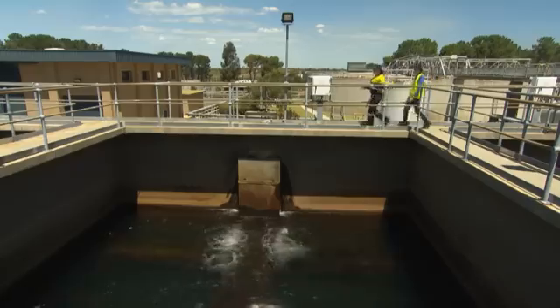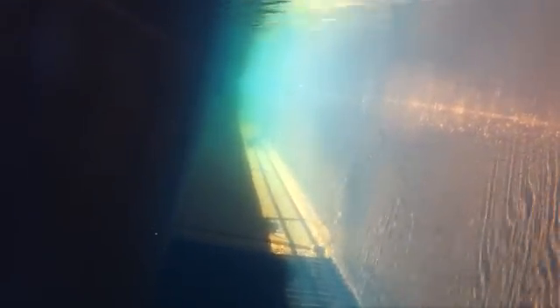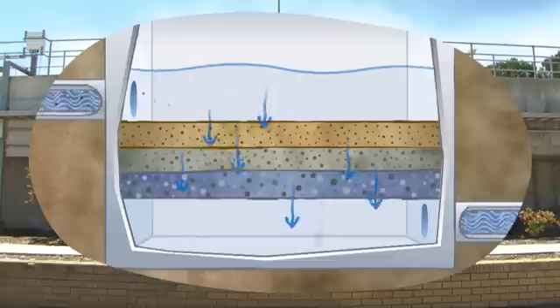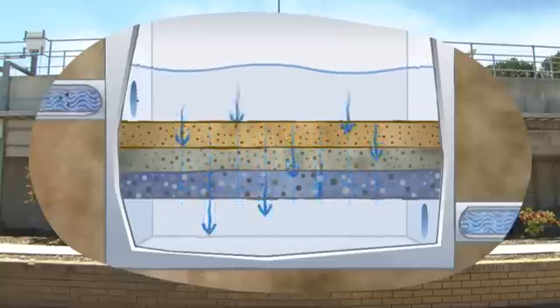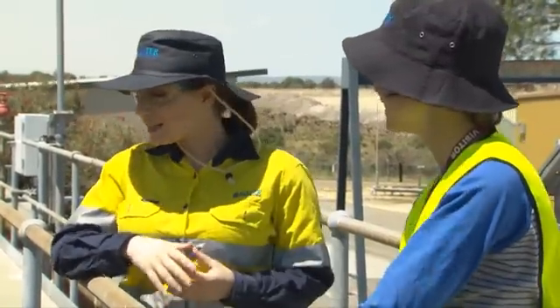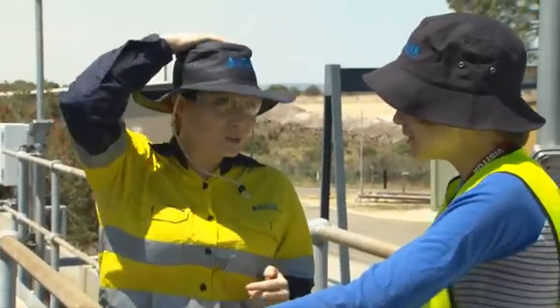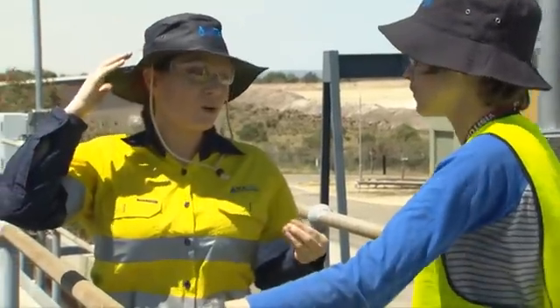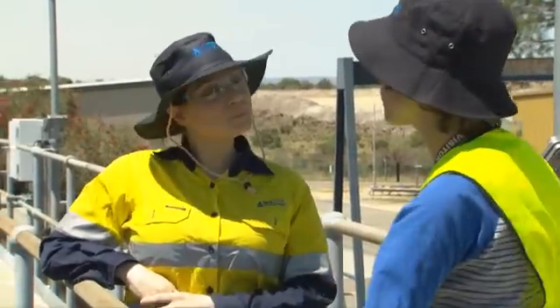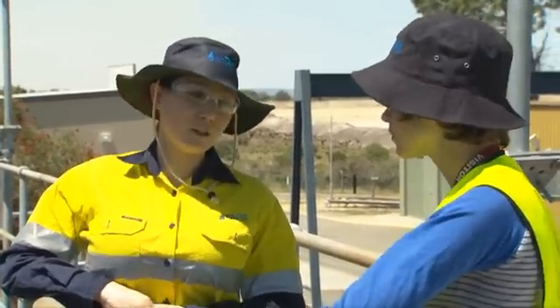After clarification, water from both the MIEX and standard treatment processes comes together for filtration. The water goes through deep bed filters containing carbon, sand and blue metal to remove any particles carried over from the clarifiers. Filters are regularly cleaned by backwashing — running water in reverse to push out particles. The backwash water returns to aeration to be treated again, and the sediment removed from the filters goes to drying beds and then to landfill sites.